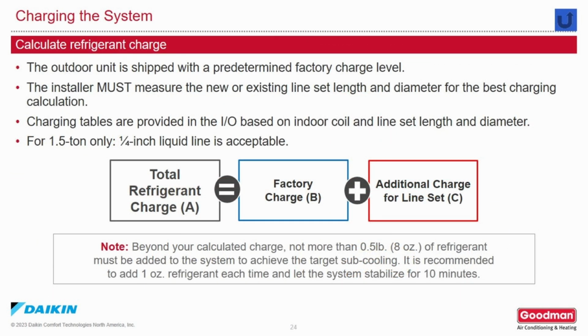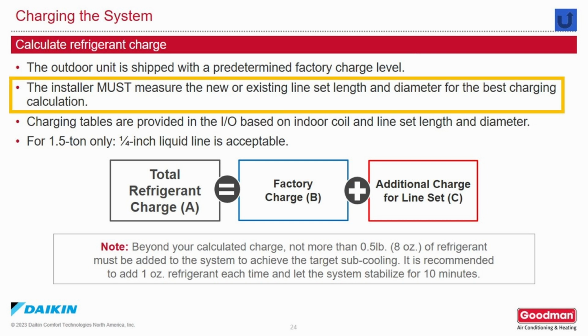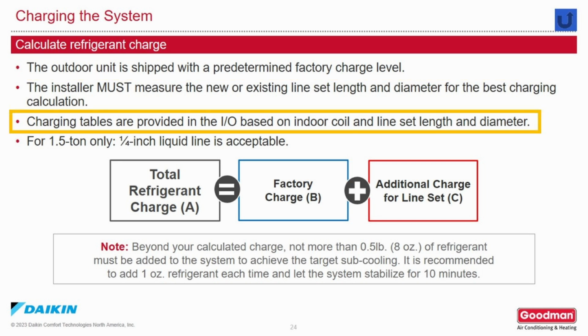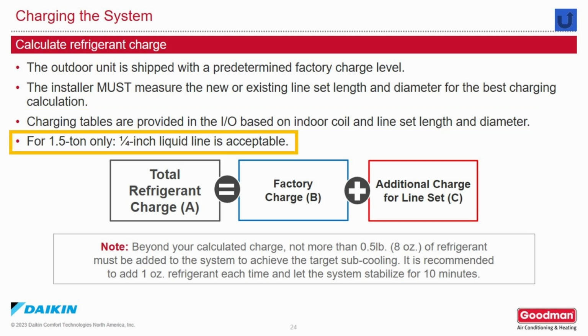So now, for charging the system, how do you calculate the additional refrigerant charge? The outdoor units are shipped from the factory with a predetermined amount of refrigerant. The factory has no way of knowing what the finished line set length will be on the job, so it's up to the installer to measure the length and diameter of the new or existing line set they will be using. Charging tables are provided in the installation manual for the outdoor unit. Only the 1.5-ton unit uses a 1/4-inch liquid line. All the other sizes use a 3/8 liquid line.